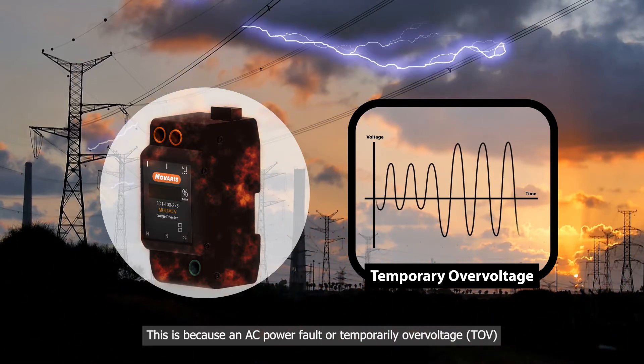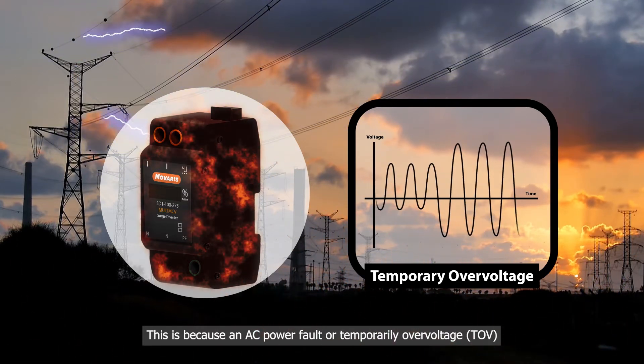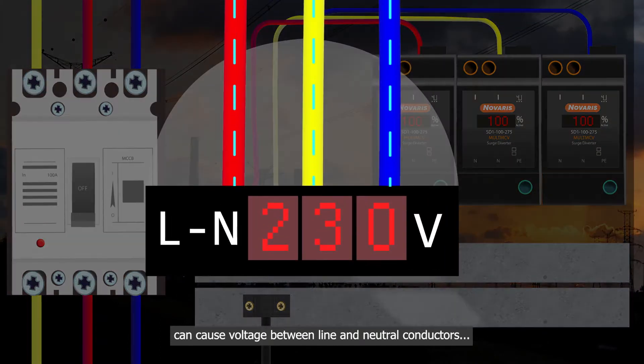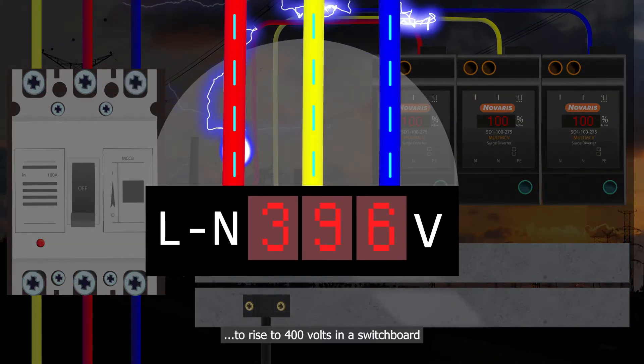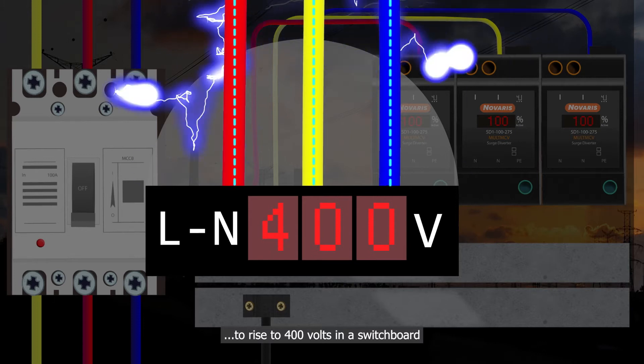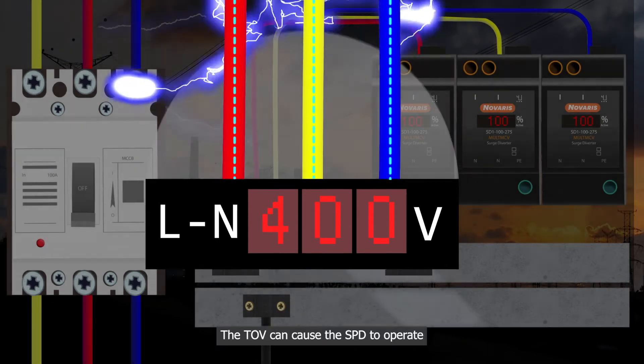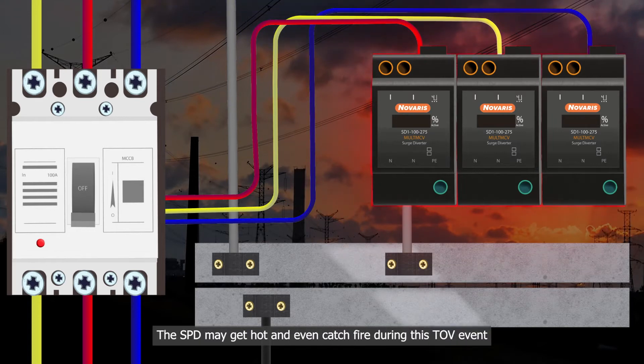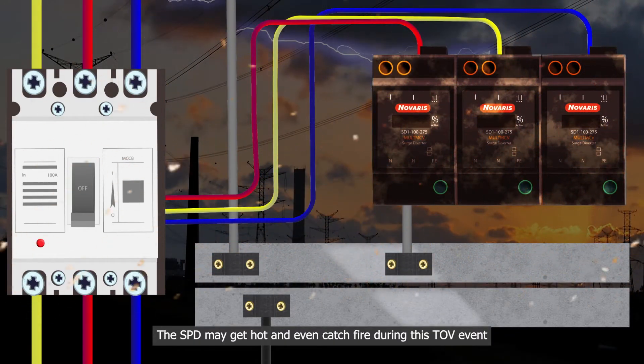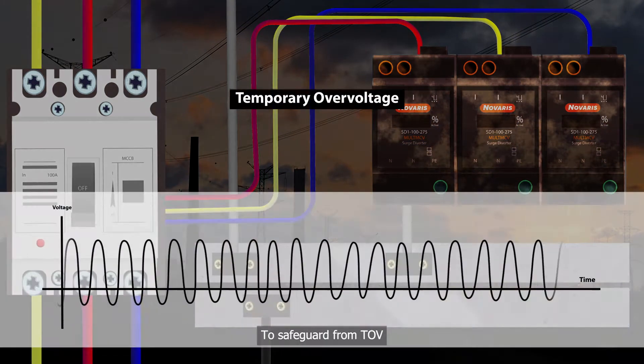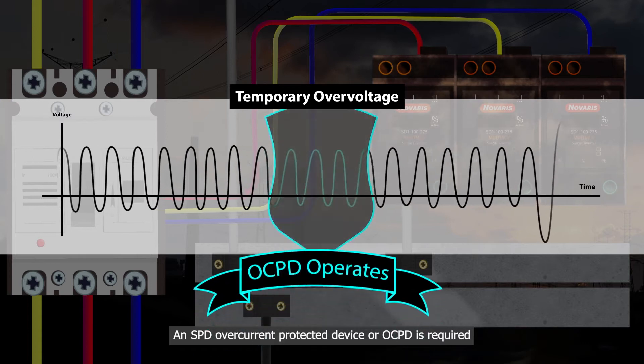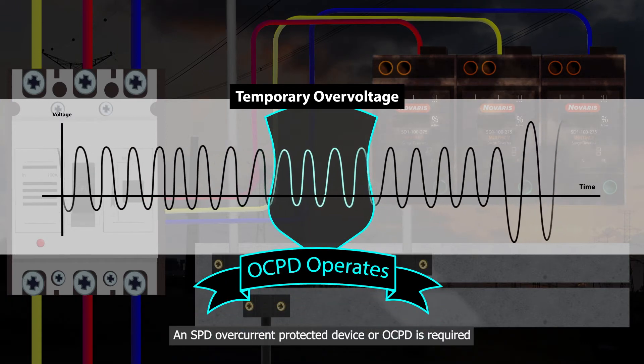This is because an AC power fault or temporary overvoltage can cause voltage between line and neutral conductors to rise to 400 volts in a switchboard. The TOV can cause the SPD to operate, and the SPD may get hot and even catch fire during this TOV event. To safeguard from TOV, an SPD overcurrent protective device, or OCPD, is required.